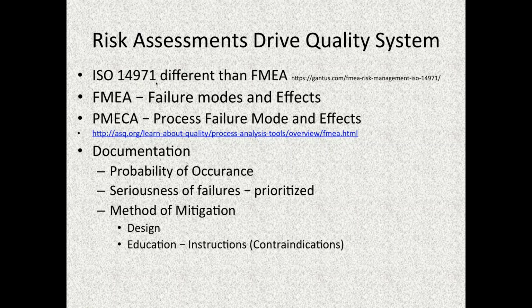Learn the failure modes and effects analysis, FMEA, and PFMEA, which is the process failure modes and effects analysis. While you can look at the device and say, here's how it will fail and here's my mitigation for the failure, if you're looking at the process of how you made it, you have to go back and say, here's how my process might fail and I could get a defective result coming out of it. Documentation of this risk assessment means probability of occurrence, seriousness of the failure, and how you mitigate the possibility for failure, either through design or through education or contraindications.